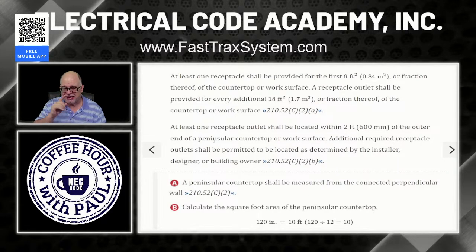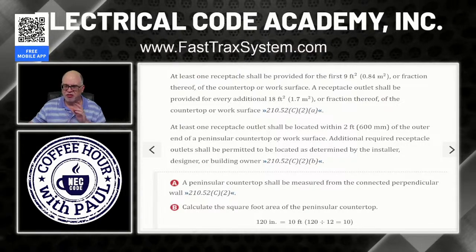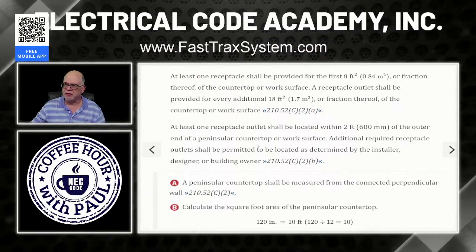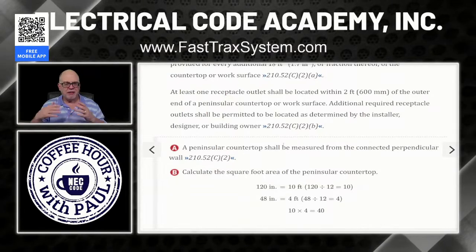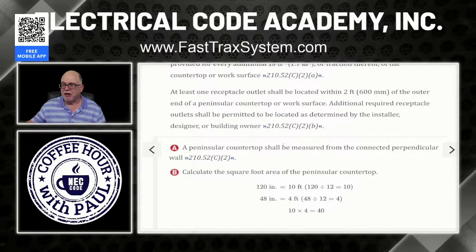That's so important. The first one, for the first 9 square feet, has to be within 2 feet of the outside edge of the peninsula. If it's bigger and has the next 18 square feet, then you can put that anywhere you want, as the installer or the owner. But I have to have at least one within 2 feet of the outside edge of that peninsula countertop surface, right? We'll look at an illustration, okay? So islands are simple. The only thing that takes a peninsula to the next level is that you have to have it within 2 feet of the outside edge of the peninsula countertop.